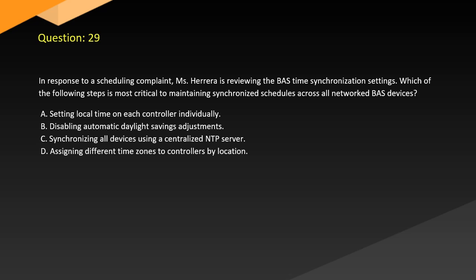Question 29. In response to a scheduling complaint, the facility manager is reviewing the BAS time synchronization settings. Which of the following steps is most critical to maintaining synchronized schedules across all networked BAS devices? A. Setting local time on each controller individually. B. Disabling automatic daylight savings adjustments. C. Synchronizing all devices using a centralized NTP server. D. Assigning different time zones to controllers by location.